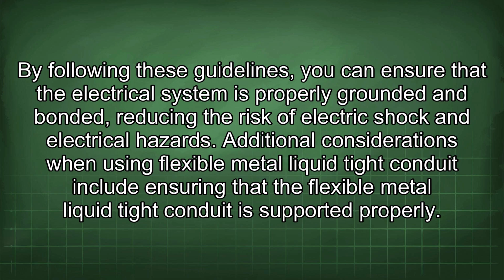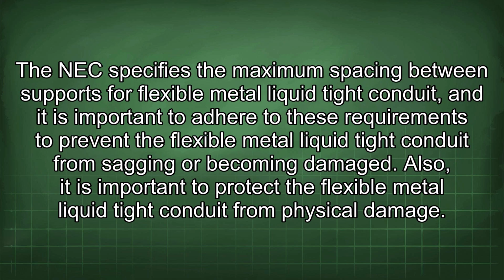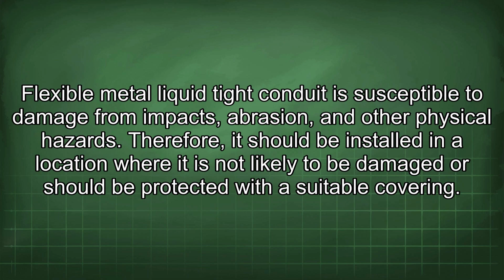Additional considerations when using flexible metal liquid tight conduit include ensuring that it is supported properly. The NEC specifies the maximum spacing between supports for flexible metal liquid tight conduit, and it is important to adhere to these requirements to prevent it from sagging or becoming damaged. Also, it is important to protect the flexible metal liquid tight conduit from physical damage. It is susceptible to damage from impacts, abrasion, and other physical hazards.